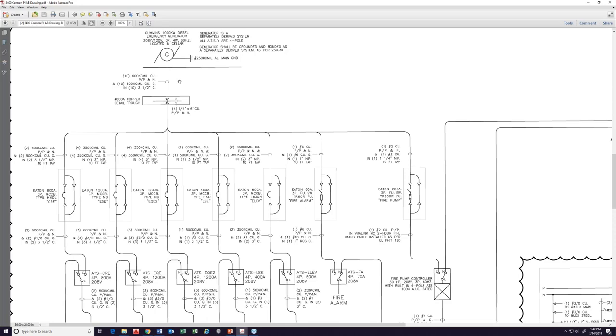There is a downside to that, because in some jurisdictions such as New York City, there is a requirement that a fire pump and fire alarm feeders must be mains. And if you see over here, this fuse switch is feeding the fire alarm, the fire pump, and this is feeding the fire alarm system. Now, these cannot be on the load side of any other breaker. They must be directly connected to the alternator of the generator. So if I would have to put a main here, I would also have to add two additional small mains at the generator, and these two devices would have to be at the generator. But for the rest of the devices, I can feed it from a non-fused switch.